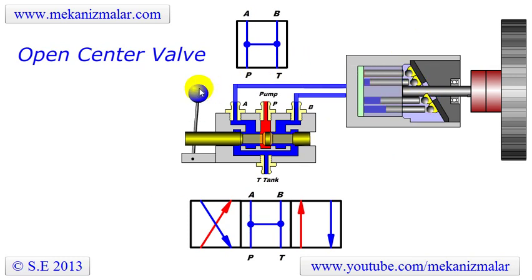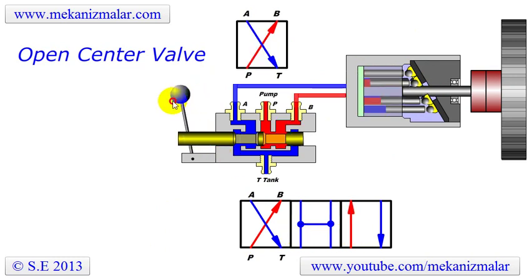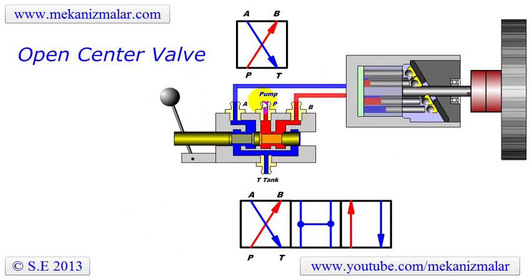The valve has three positions to control the direction of the oil coming from the pump. When the control arm is pulled to the extreme left, the pressurized oil coming from the pump is diverted to port B of the valve. At the same time, the low pressure oil coming from the motor is connected to port A of the valve, which is open to port T.